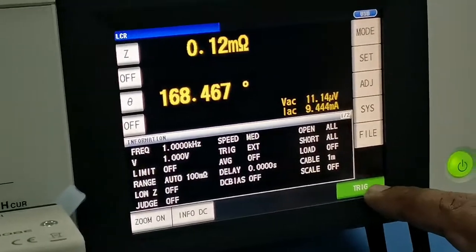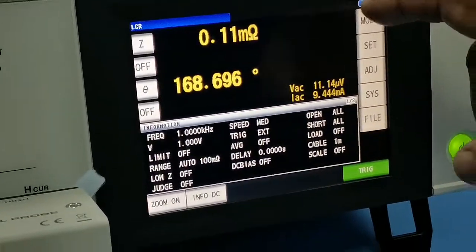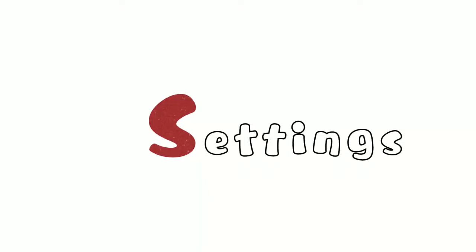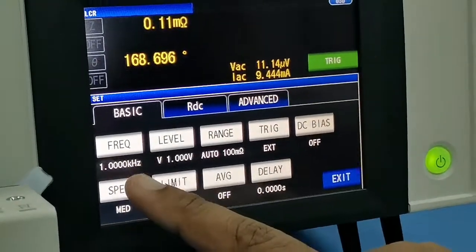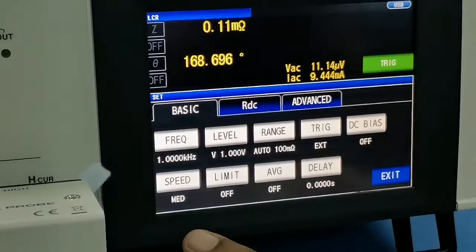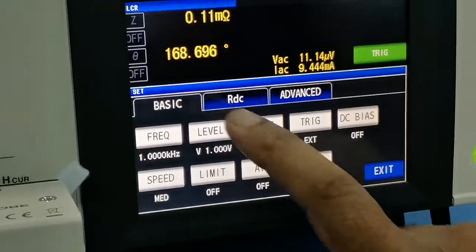Now we can do the setting. There you can do the setting — this is for the calibration. You can select the frequency, level, range, trigger point, DC bias, speed, limit, average, delay — all you can do.